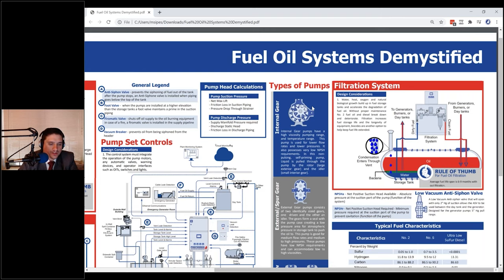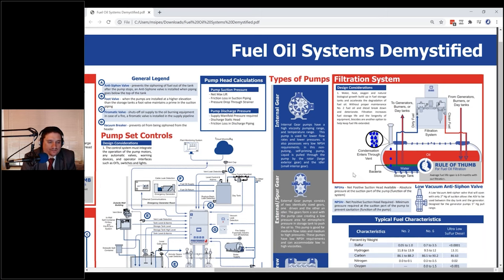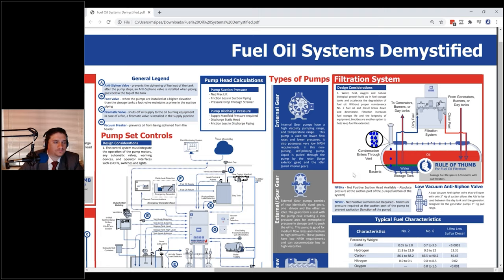We also have an item on here — our low vacuum anti-siphon valve. That's a new item just coming out. We noticed a need for anti-siphon valves between the generator and a day tank, where a generator couldn't pull enough to get through some other anti-siphon valves. So our R&D department created this low vacuum anti-siphon valve to be placed between a day tank and a generator.